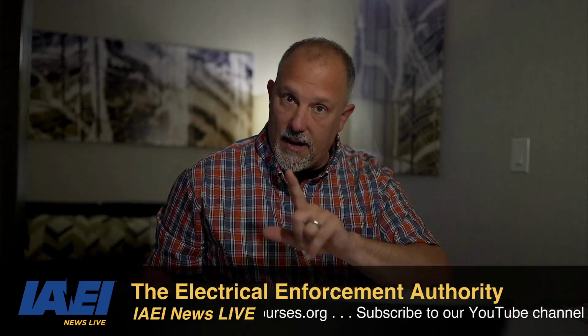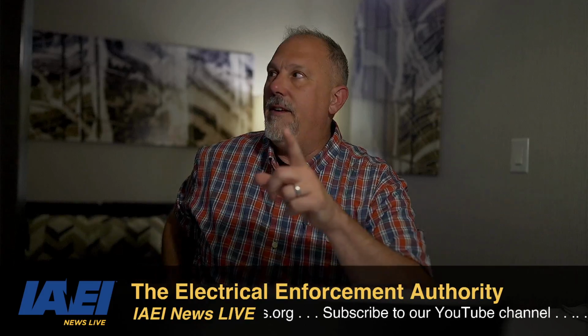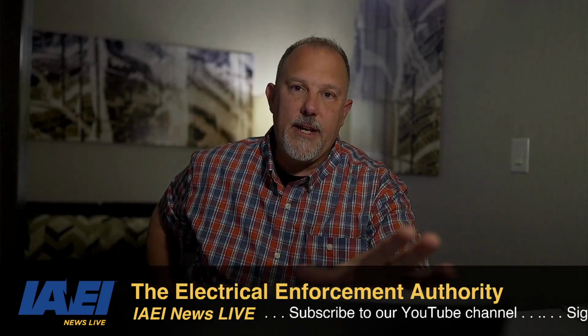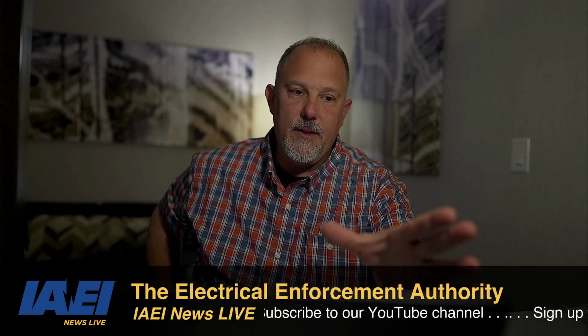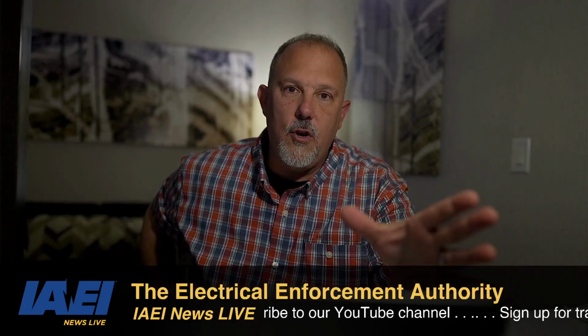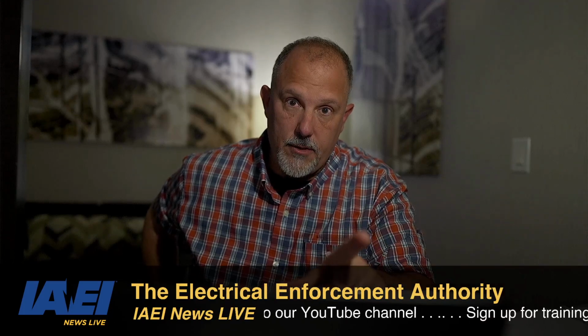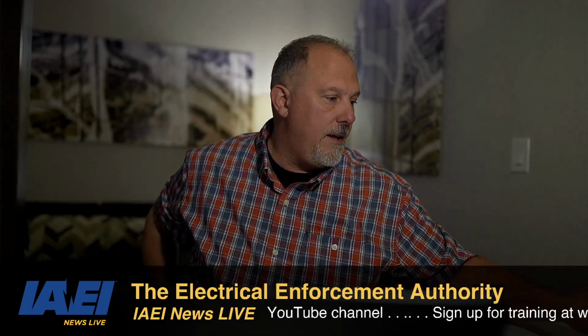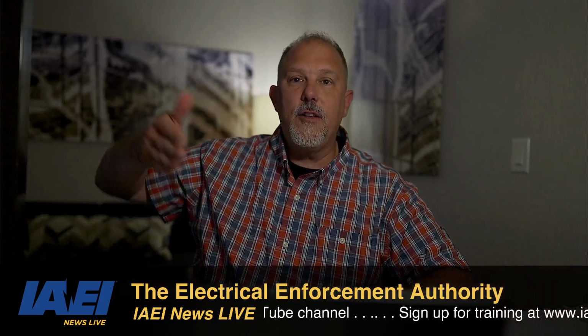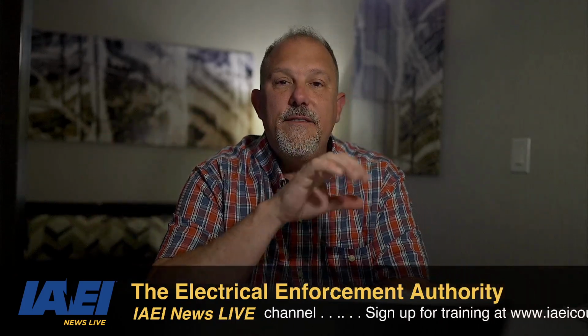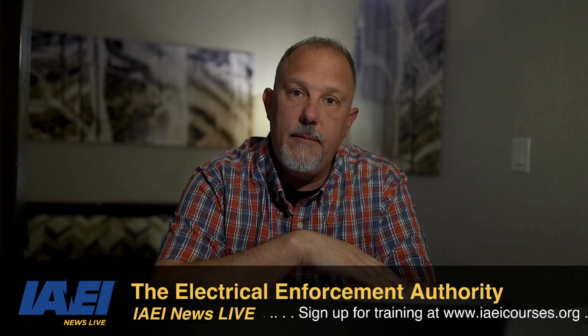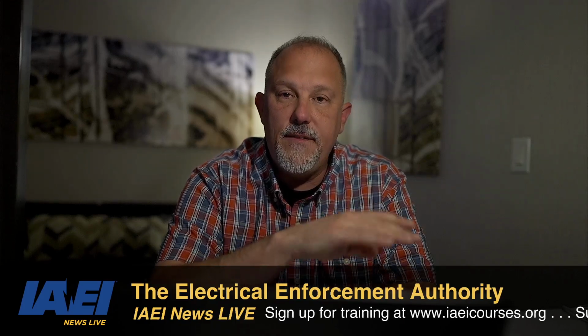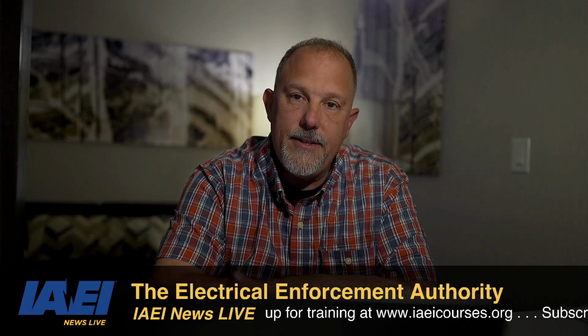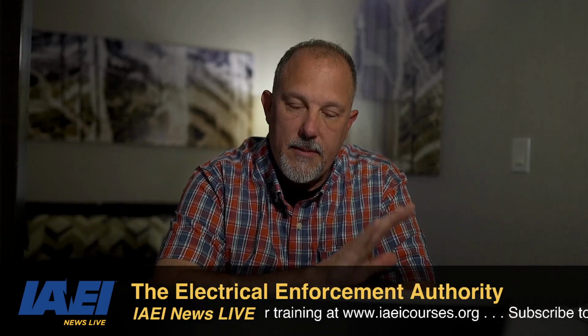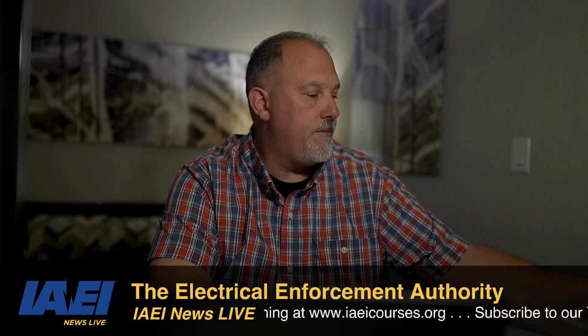But first off, the first thing I want to make sure that we all understand are basically the types of overcurrent protective devices, circuit breakers. There are medium and low voltage installations. I'm going to focus on low voltage circuit breakers. That would be 1,000 volts and below: 1,000 volts AC, 1,500 volts DC, and lower in voltage rating. I'm not going to talk about medium voltage right now.